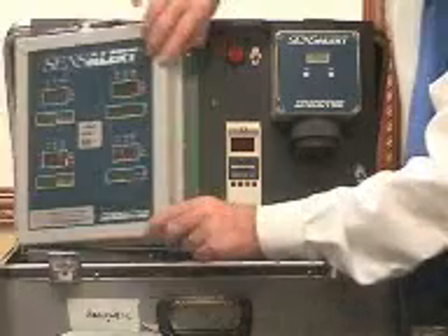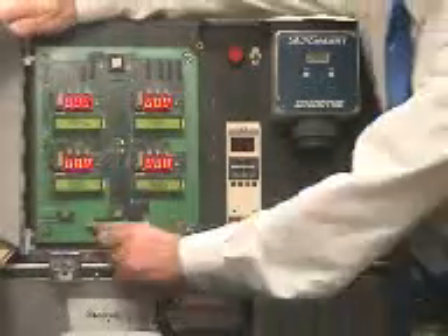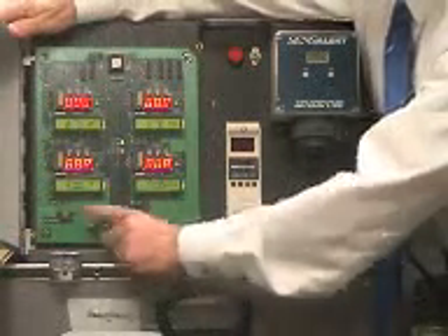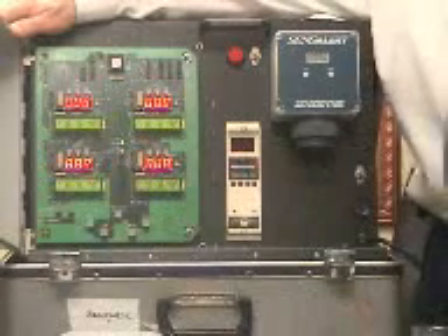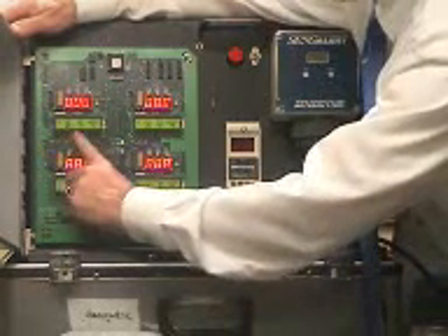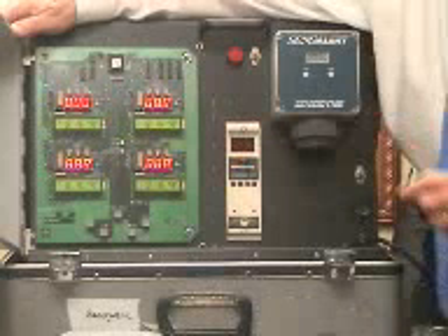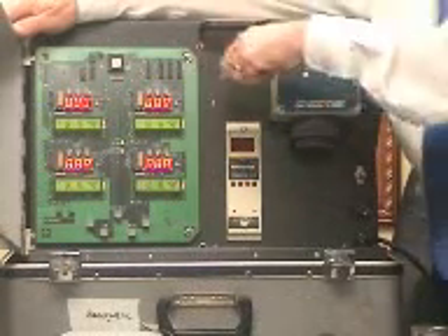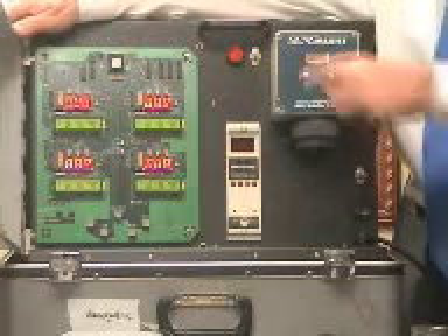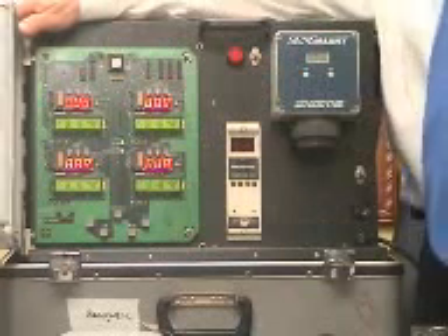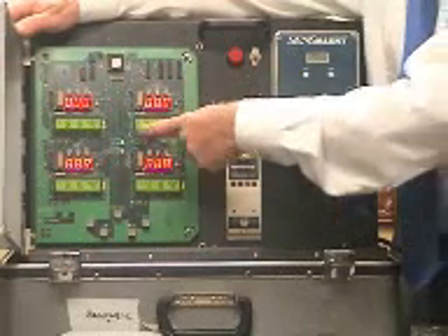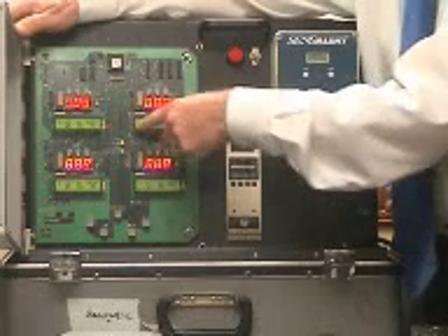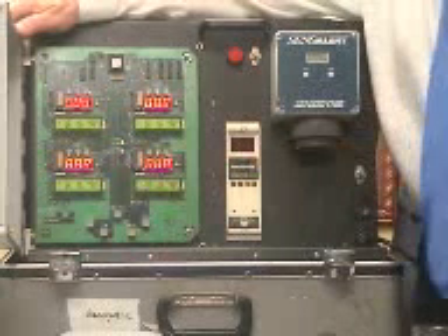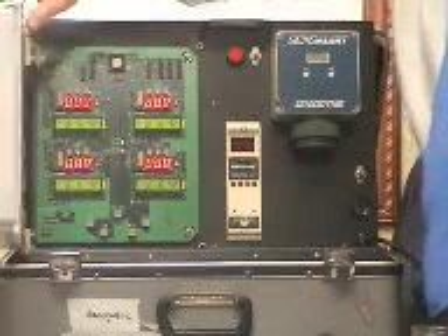To check the alarm set points from the factory, you touch the next button and it displays the 3 alarm settings. Ammonia from the factory is set at 25, 35, and 75 ppm, 3 alarms, and inside the controller there are 3 relays available just for that channel if you want to utilize them. And if your company wants to, or if the customer wants to adjust the alarms, you simply change the alarms the way they want the alarm set.